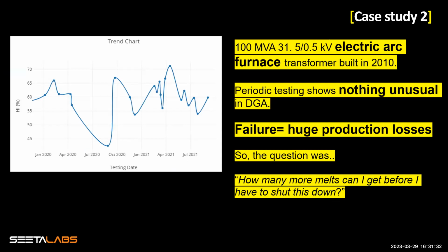As you can see on the screen, the health index of that transformer over the years kept on fluctuating. And no matter how much they were filtering or degassing, the health index wouldn't stop fluctuating. Although these assets are highly stressful assets, this should not happen. So what was causing it?